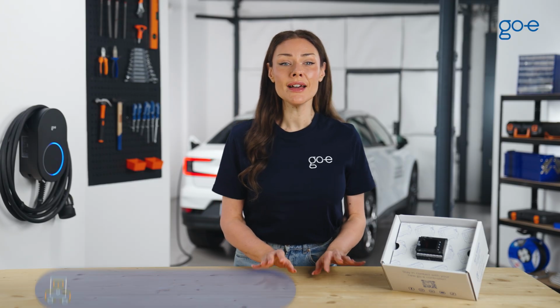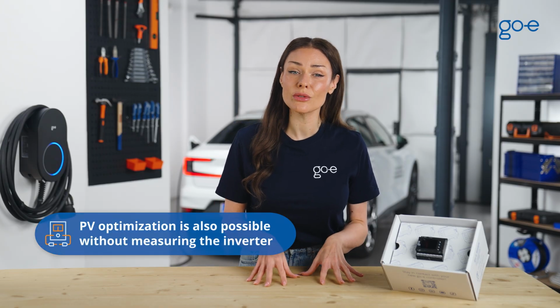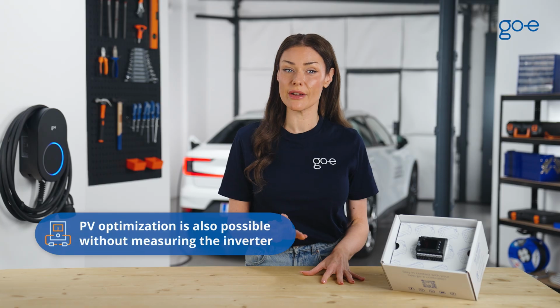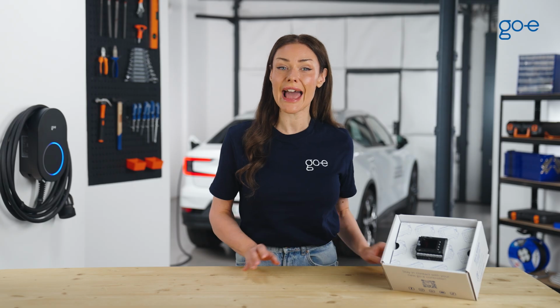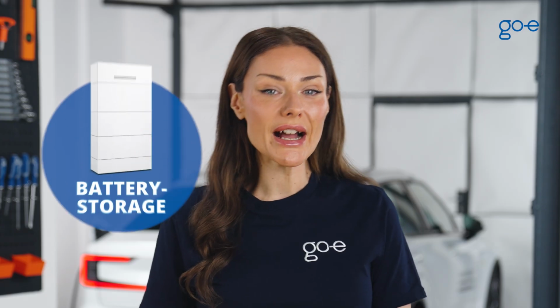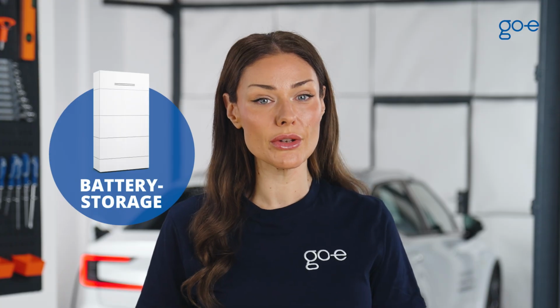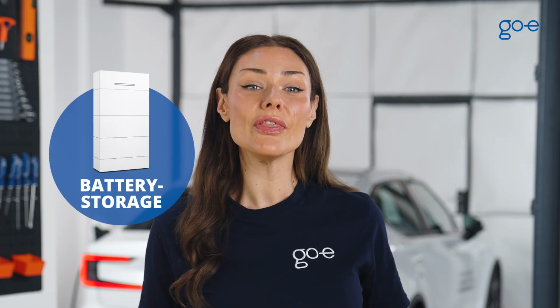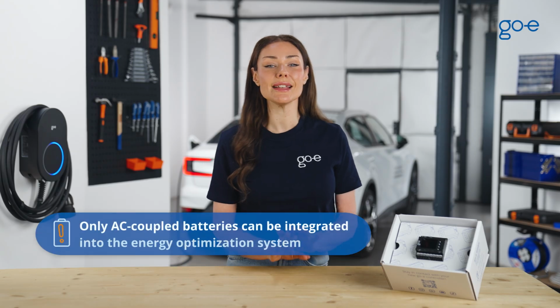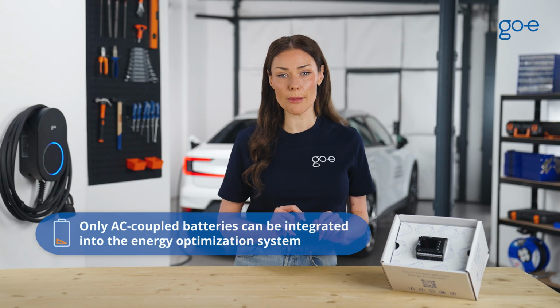Just a quick reminder, PV optimization is also possible without directly measuring the inverter's production. However, with an AC inverter, using a sensor allows you to additionally see how much power the system is generating in total. If you have a battery storage system that should be included in your energy optimization, then use one current transformer to measure one phase of the battery system. Please note that this is only possible with AC coupled batteries.